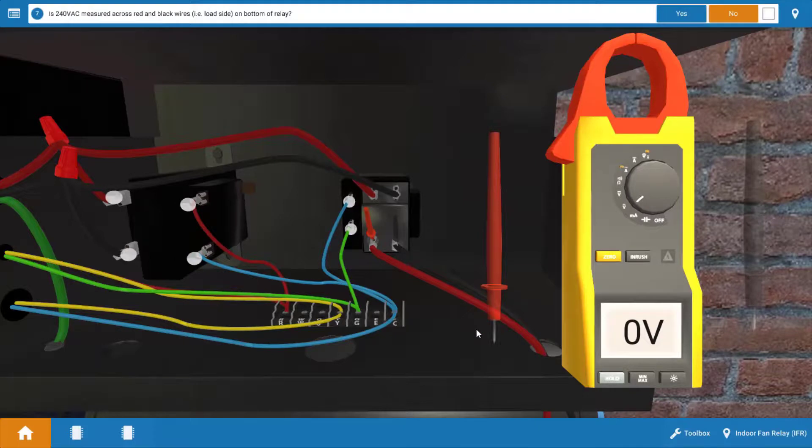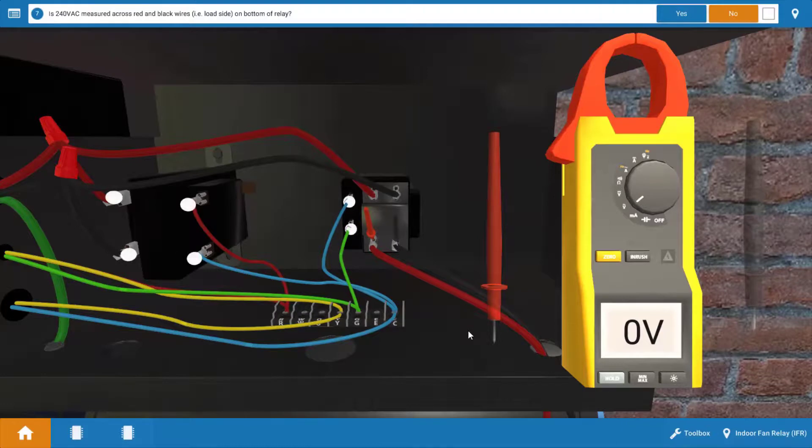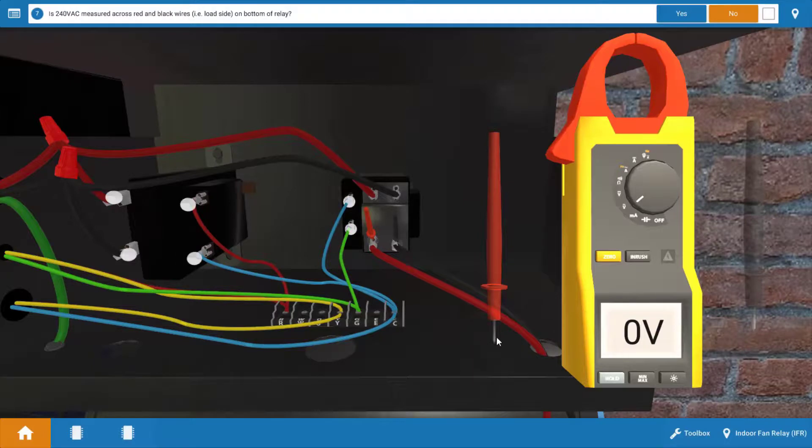Now that means these contacts are open. Now we haven't determined whether it's the coil or the contacts, but that doesn't really matter. We've got power to the coil. The contacts should be pulling in. The relay is going to have to be replaced.